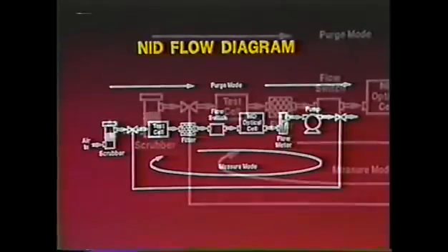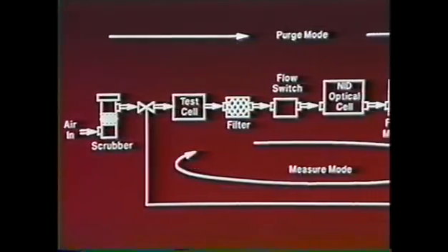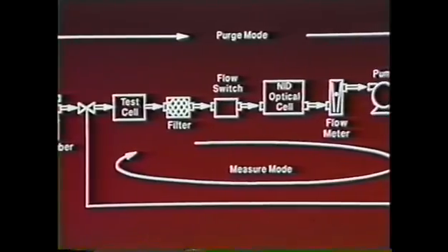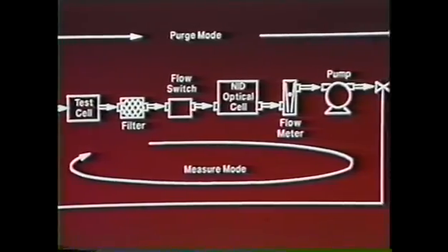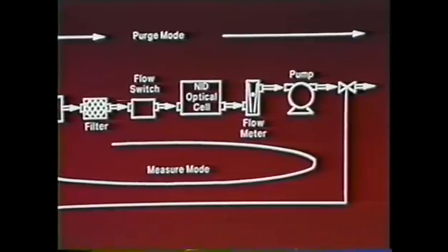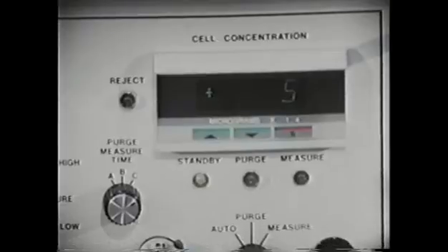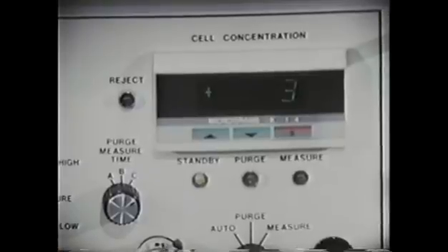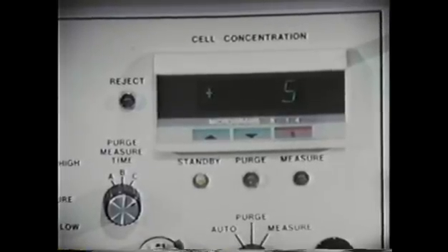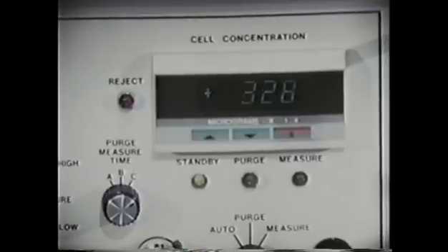As it is heated, the fluorocarbon trapped inside a defective part is vaporized and detected electronically by the NID analyzer. This flow diagram illustrates the process. Instead of depending on the operator to observe fluid leaking from the package, the NID uses an analyzer to detect the escaping vapor. The NID analyzer measures the concentration of fluorocarbon molecules within the system.